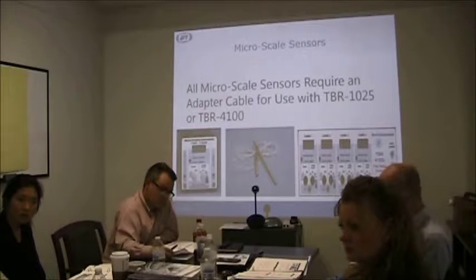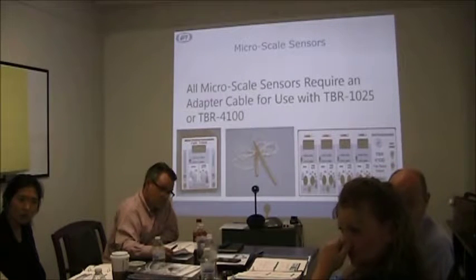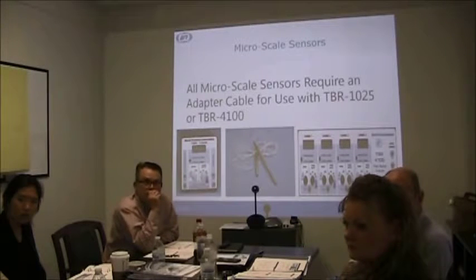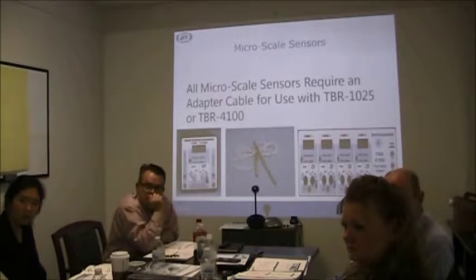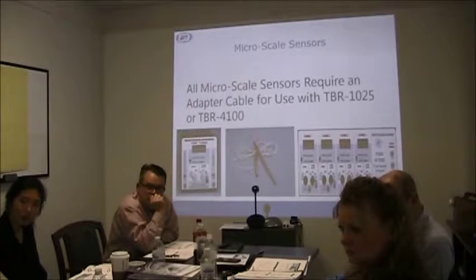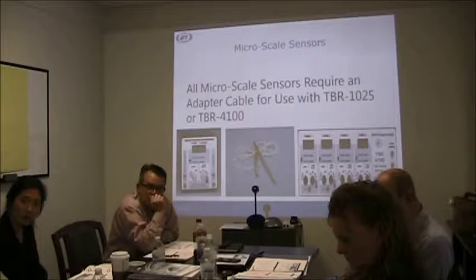Will it actually be detecting different species other than the one you're looking at if you're off from the normal poise voltage? No, it won't detect different species. It's just going to have different values for your baseline current when you're recording data. So the only thing that's going to come into effect is concentration, where you will potentially have a different effect if you're trying to measure super high concentrations with our sensors.